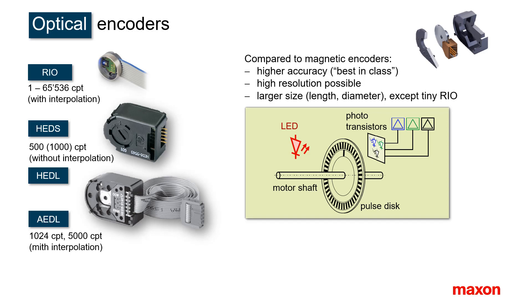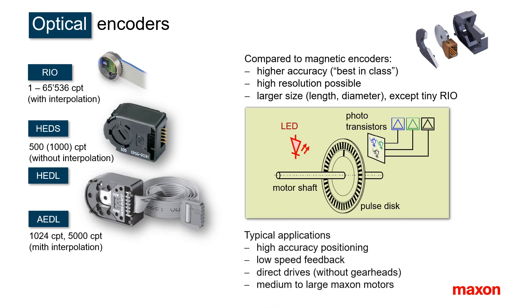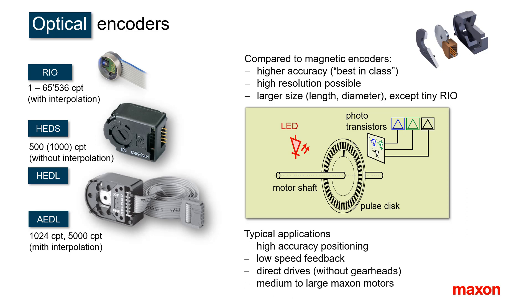Optical encoders are the best in class when it comes to accuracy and often also resolution. However, they are typically larger in size than many other Maxon encoders, which makes them not very suited for the smallest motors — the RIO being the exception that proves that rule. The high resolution combined with high accuracy makes them a perfect match for high-precision positioning and the feedback of very low speeds. Optical encoders of highest resolution are best in direct drive applications with powerful motors.